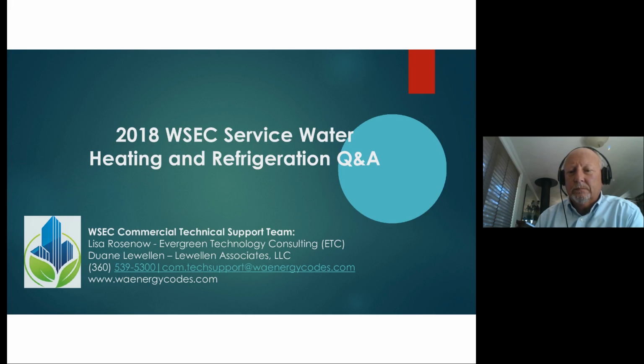Okay, so over in chat, we've got a few more questions. Randy Stabno asks, are thermostatic valves an acceptable means of balancing for multiple branch recirculating systems? Yes, I would say that they are. On the individual branches, whether it's a thermostatic valve or a circuit set or balancing flow control valve, that would be acceptable. It's just that what's not acceptable is to have a valve that restricts all of the water heating demand, or that's on pressure boosting systems. But I would think if you've got some means of balancing individual branches on multi-riser, whether it's thermostatic or flow, that would be acceptable. Yeah, I would agree with that.